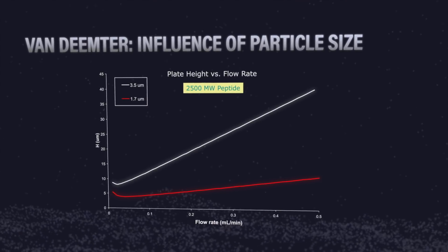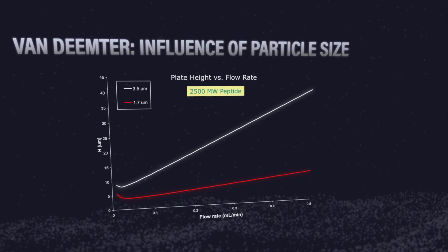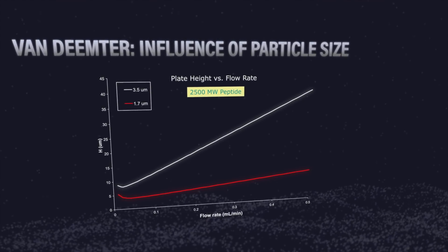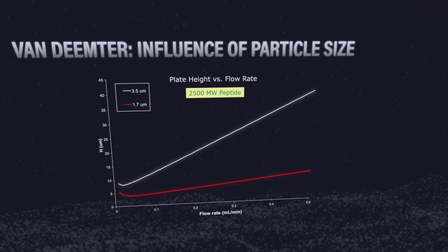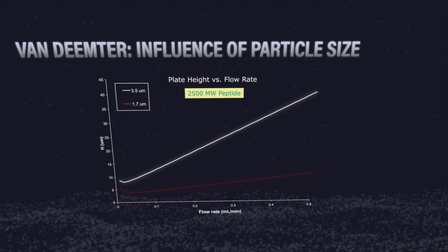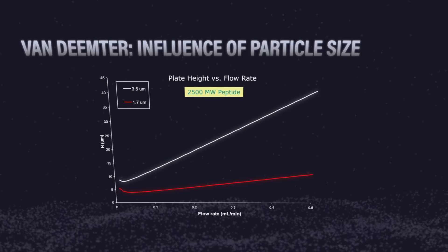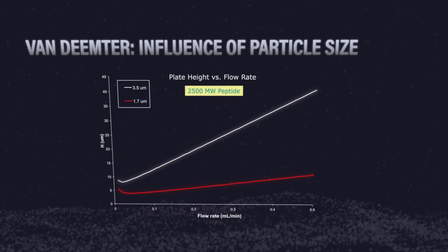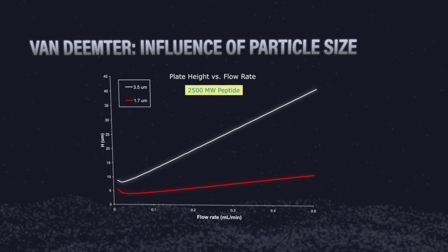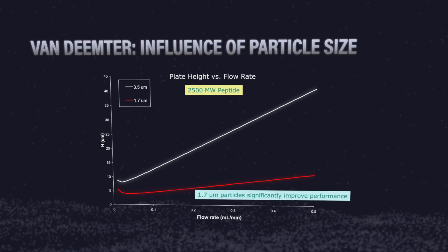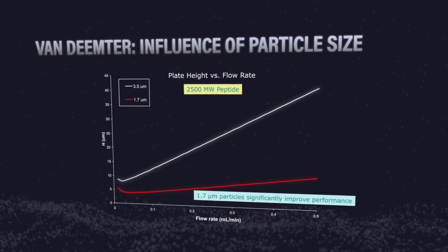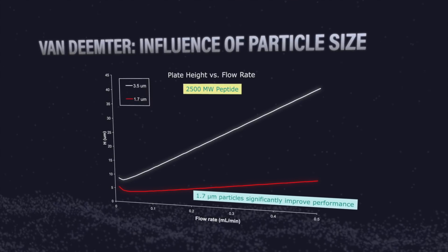We were also able to look at the difference in particle size specifically for one peptide. We made a van Deemter curve to look at the difference of a 2,500 molecular weight peptide on 3.5 micron particles versus 1.7 micron particles. It's pretty clear from these curves that with the 1.7 micron particle, you can get much better performance not only in efficiency, but it also gives you a wider range of flow rates from which to choose to get that improved efficiency.